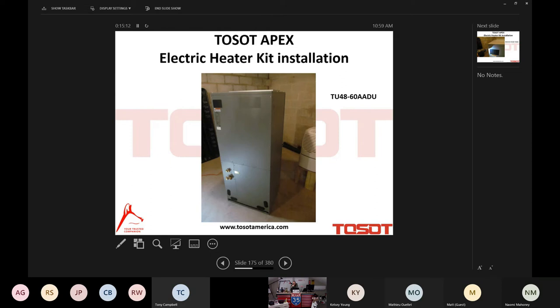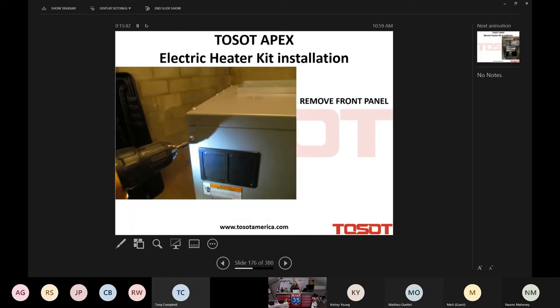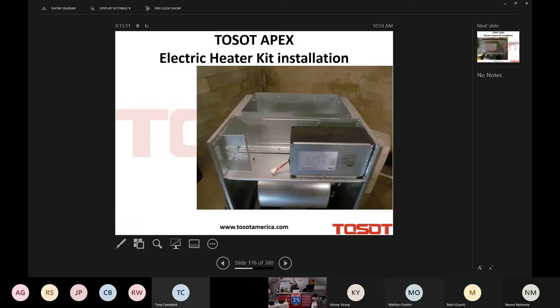Now, I will tell you this. As I mentioned to you earlier, these systems, the Ultra Heat system, the Apex system, are capable of rated capacity of heat down to negative 30 Fahrenheit. Now, if it ever gets below negative 30 in central Pennsylvania, it's probably the apocalypse. I probably have bigger issues than my Apex not being able to maintain temperature. But that aside, I'm ready for the apocalypse, baby. I put the electric strip in there, and that's what we're going to do here. We're going to remove that top front cover, and then we're going to remove the front top cover. There's a little half panel, if you will.